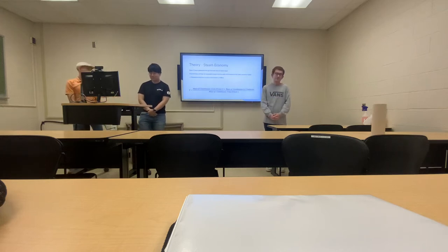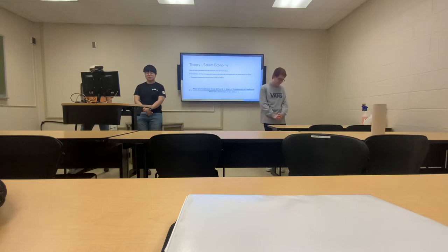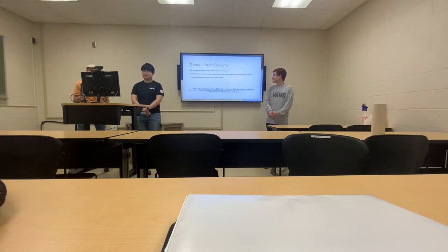In terms of the steam economy, this is a mass basis for quantifying the functionality of your evaporators. It's the amount of steam that you can generate through the evaporator train for a single unit of mass that you put in. If you have no heat loss and you put in saturated steam, as it condenses out, the heat of evaporation transfers into the water component of your system. That means the same amount of heat of evaporation that exited the steam would go into the water, and you could theoretically evaporate equally as much water if you had no heat loss.